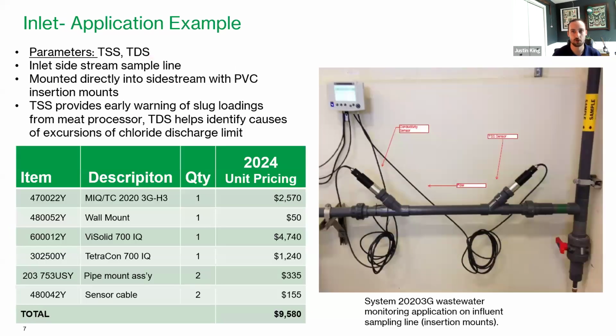And so next I want to show you an application example. In this application, we've got a TSS and conductivity sensor installed in the inlet of a plant. These sensors are actually mounted into a side stream application, which is plumbed into a 2-inch PVC pipe and utilizes insertion mounting. So you can see the two sensors there, and then those sensors actually connect into our YSI 2020 controller, which will go back to a SCADA or PLC, or it can be used just as a local display as well.